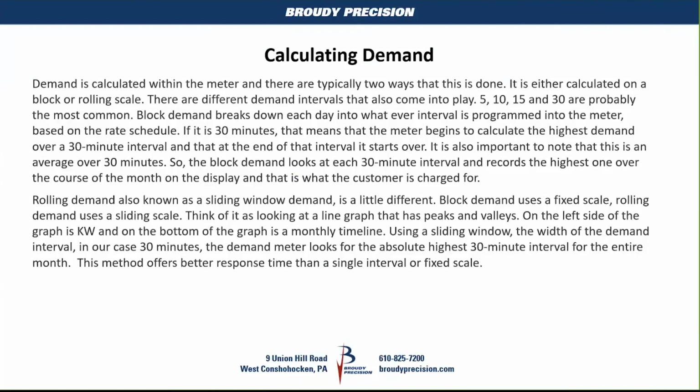But very often we don't know where that 30 minutes begins and where it ends, that the utility company or the meter on the building starts and ends. That's the problem with the block. We have no idea when that half an hour was started. Like I said, it was started at 9 o'clock. Well, what if it started at 9:06 and it ended at 9:36? So we don't know where that half an hour is.